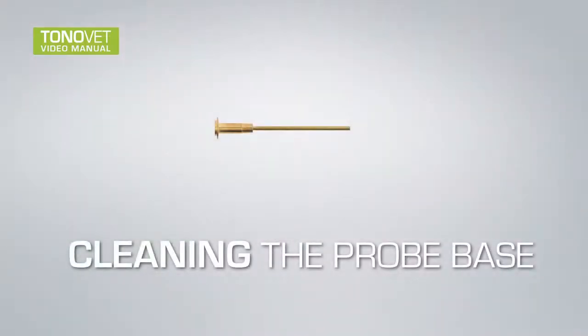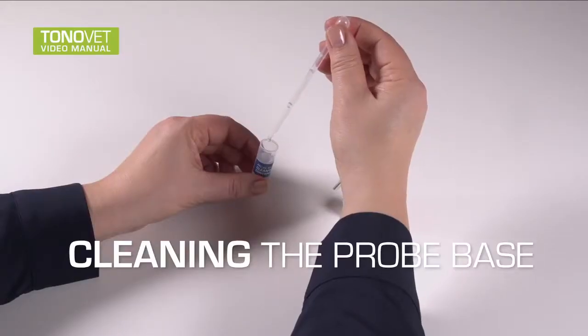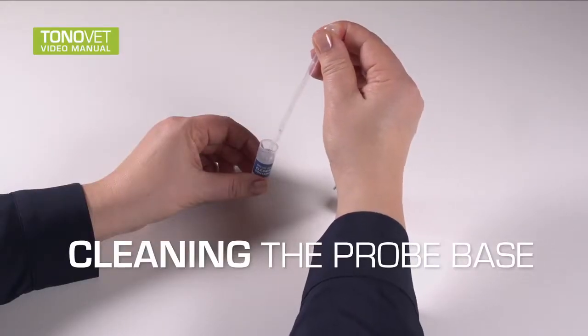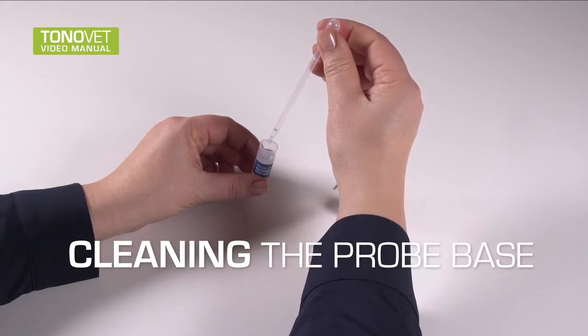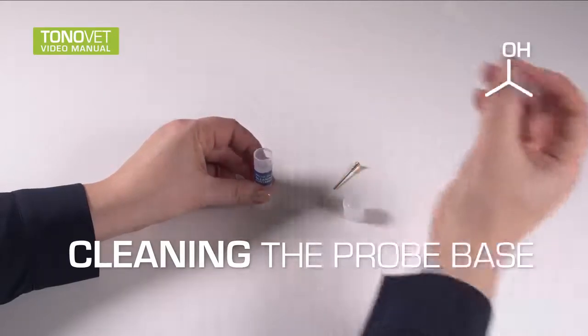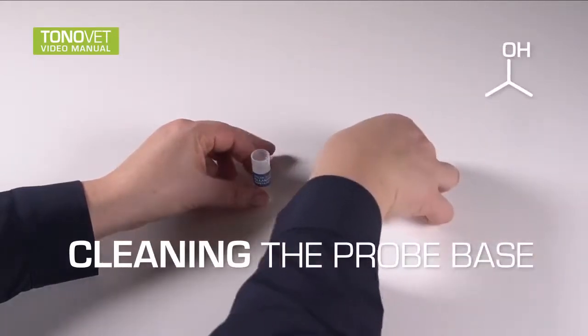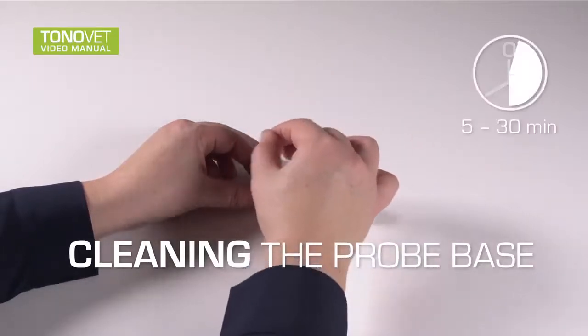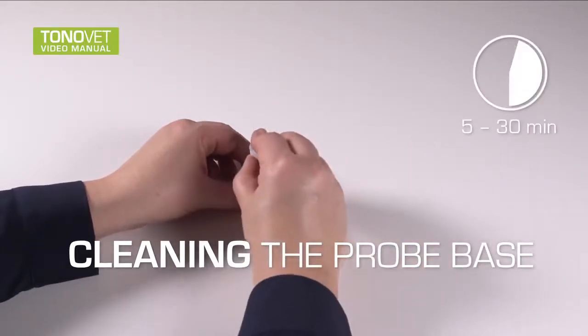Cleaning the probe base. The probe base can be reused after careful cleaning. Make sure the probe base is completely dry before using it, and replace the probe base with a new one in 2 years. Fill the probe base cleaning container or other cleaning container with a minimum of 70% isopropyl alcohol. Soak the probe base in alcohol for 5 to 30 minutes.